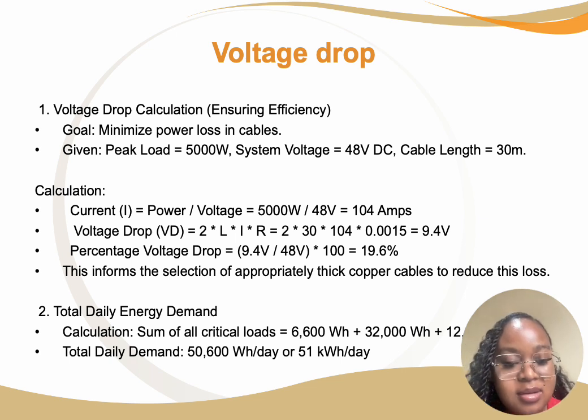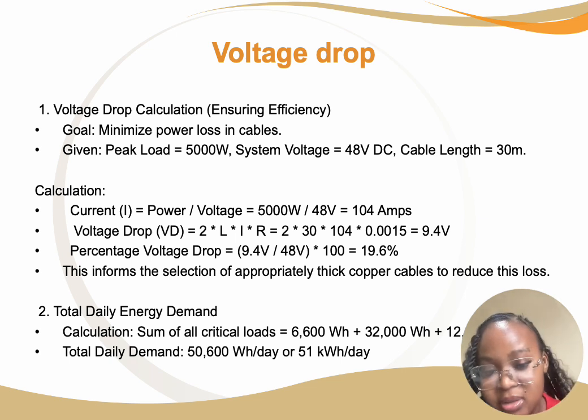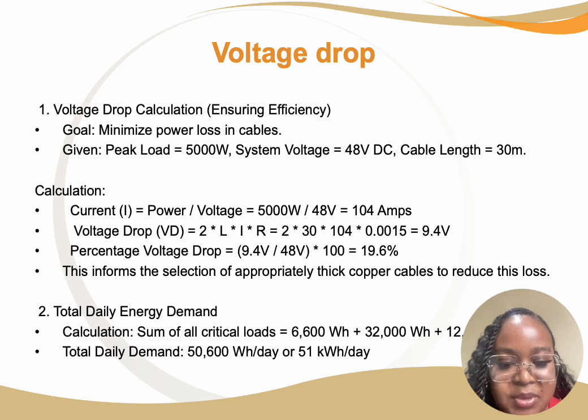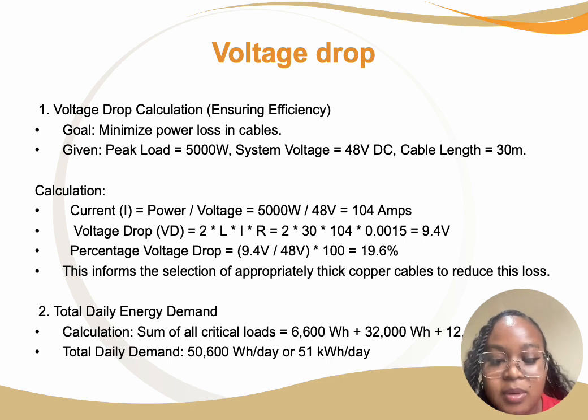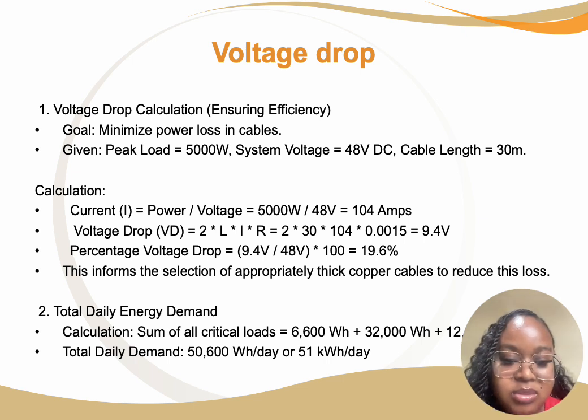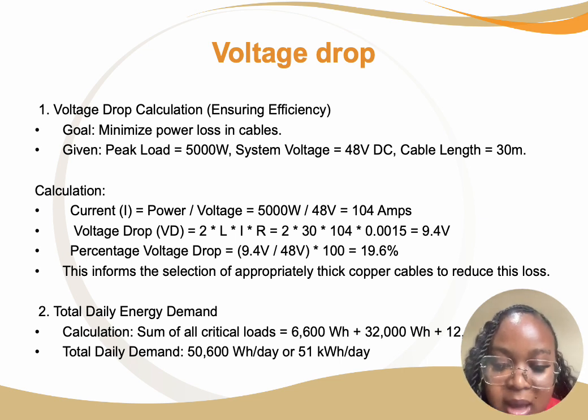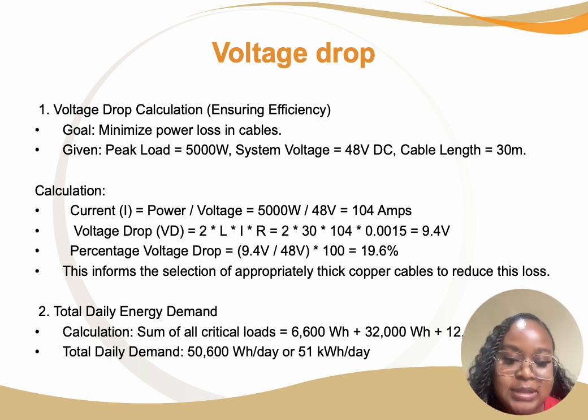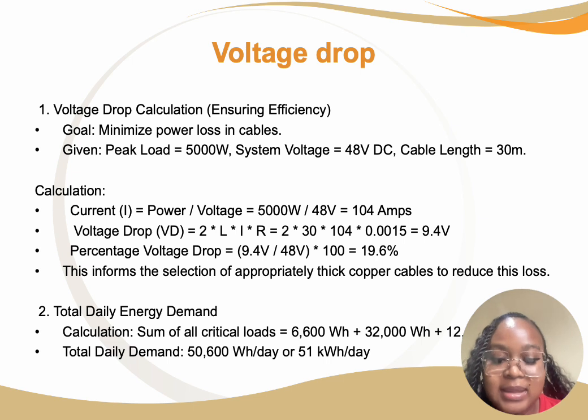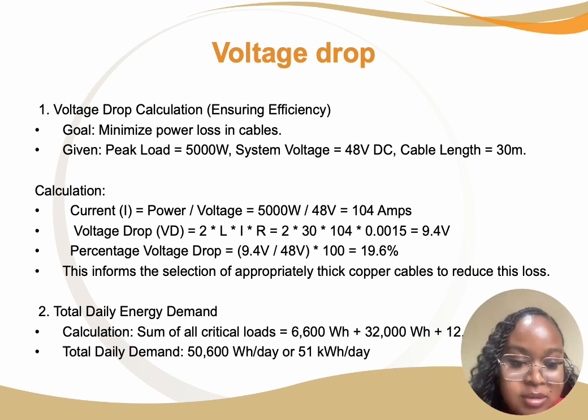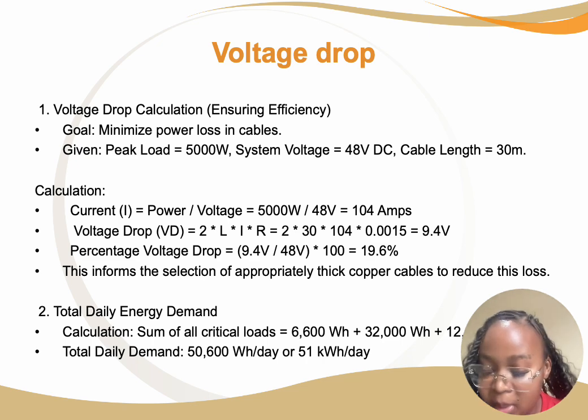Then we calculated our daily energy demand. To calculate this, we summed up all the critical loads, all the important loads basically. So we have 6,600 watt hours plus 32,000 watt hours plus 12,000 watt hours. So our total daily demand is 51 kilowatt hours per day, or 50.6 thousand watt hours per day. So these are the calculations of our daily energy demand and our voltage drop.